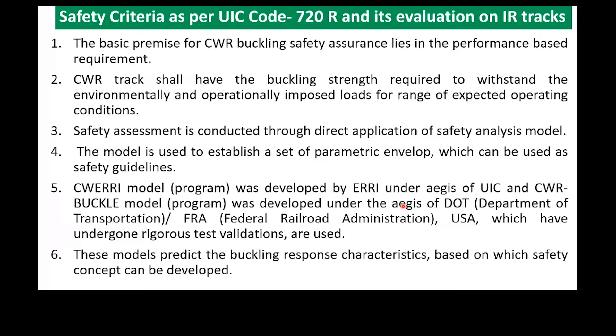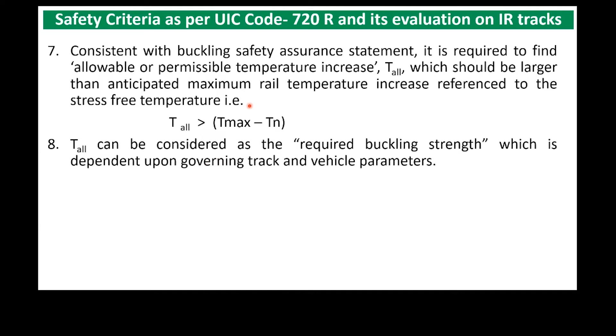Here they have given a T allowable, the concept of T allowable. Maximum temperature which can be allowed when the buckling will not take place. We have seen that T max is the maximum temperature where the buckling will take place. And this T max is the maximum temperature increase with reference to stress-free temperature. That is T max minus Tn. Tn is the neutral temperature. So T allowable should be more than the T max minus Tn. T allowable also can be termed as required buckling strength. T allowable must be the required buckling strength for buckling not to take place. T allowable can be further used to form a safety criteria for buckling response.